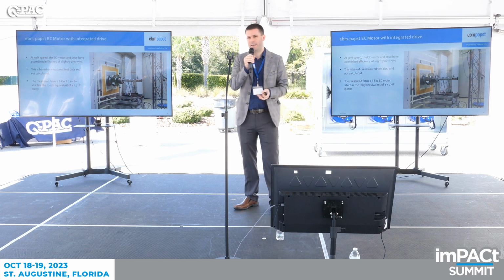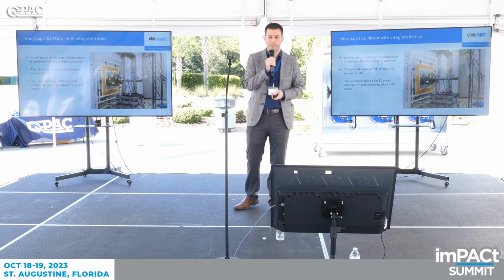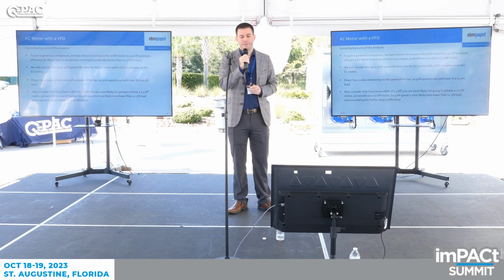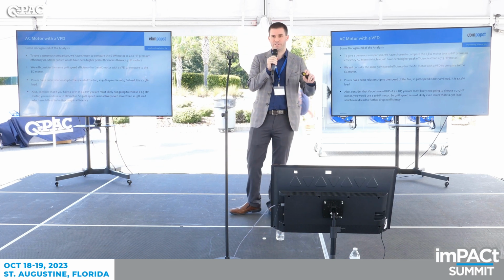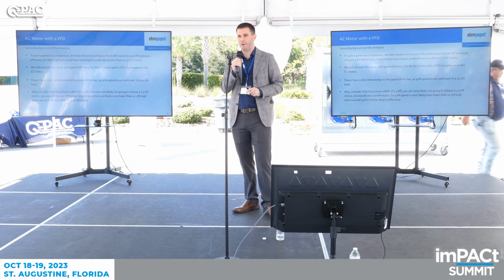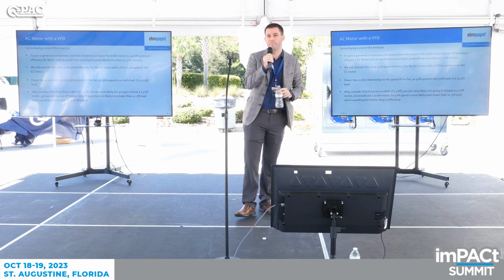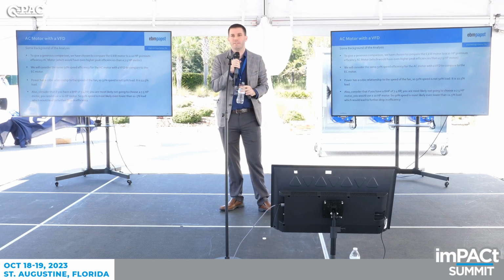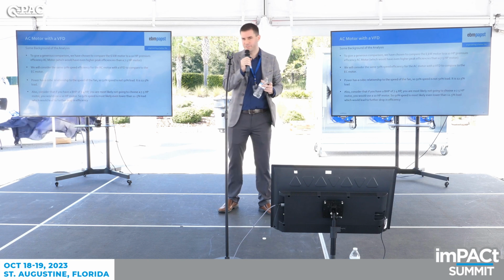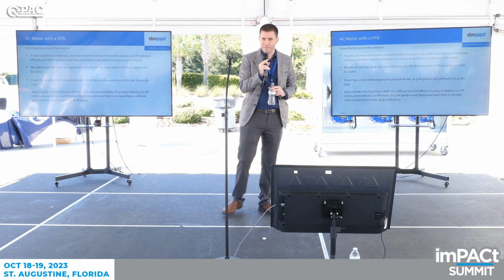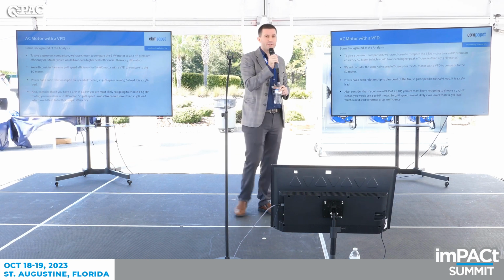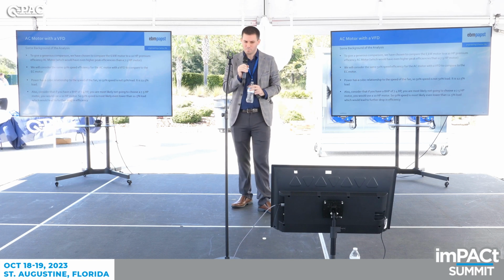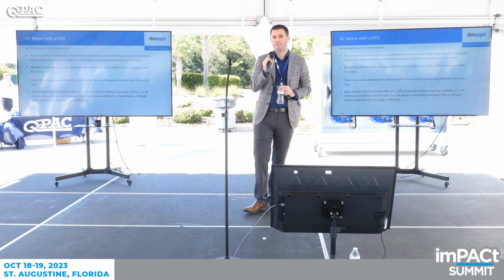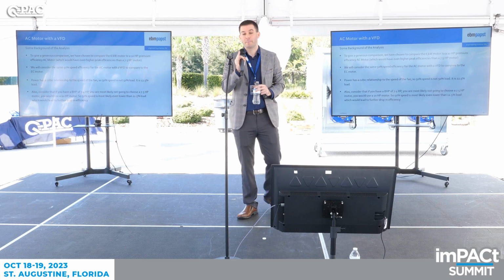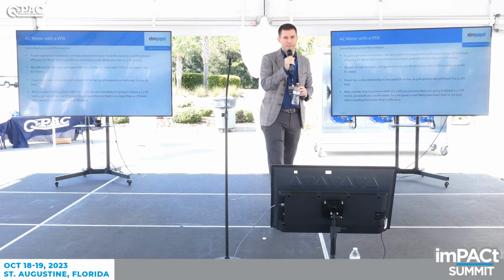And we did a 6 kilowatt fan, which is about 7.5 horsepower motor. So to give a generous comparison, we compared a 6 kilowatt fan, which is 7.5 horsepower, to a 10 horsepower motor. 10 horsepower premium efficiency motors have a higher efficiency than 7.5 horsepower. We also considered 50% speed again. But one thing to keep in mind is power is cubic to the speed of the fan. So 50% speed is not 50% load. 50% speed is actually 12.5% load.